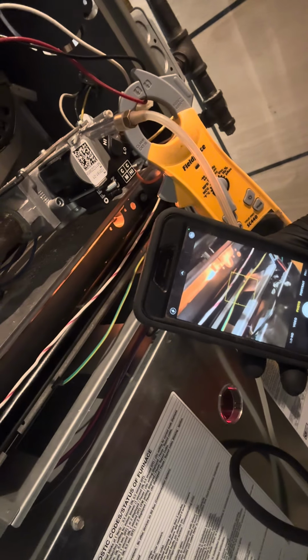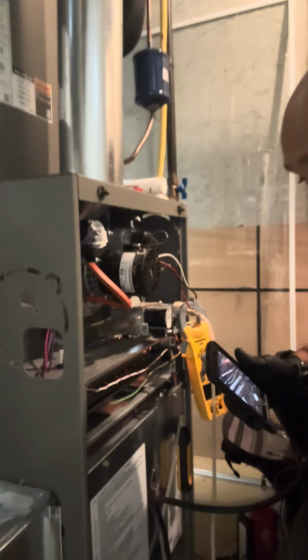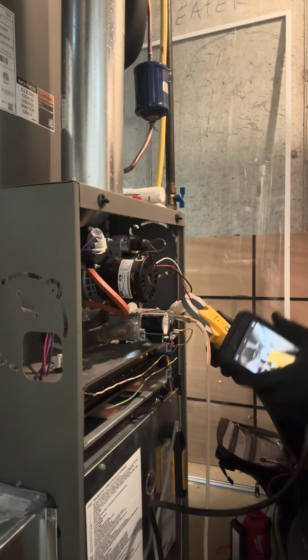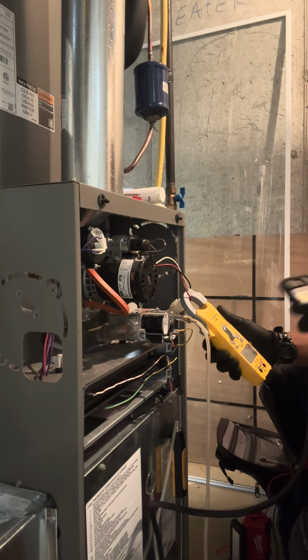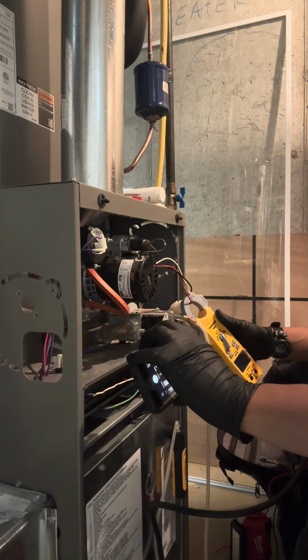I probably didn't show you on camera, but I tested that already to make sure the lines were proper. I'm going to check our inducer motor amperages, which are nice. Our flames have shot across. We're watching those flames. You want to come in here and watch these flames with me? I don't know if you can see. There you are. So I'm checking for that nice blue flame, and I'm watching for any wiggle in the flame as soon as the blower motor kicks on. Because like I said, those heat exchanger cells are sealed cells, and none of that air from that blower motor should be getting in, interfering with those flames. So we're going to watch, make sure we got no wiggle.